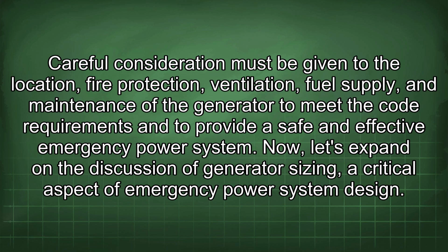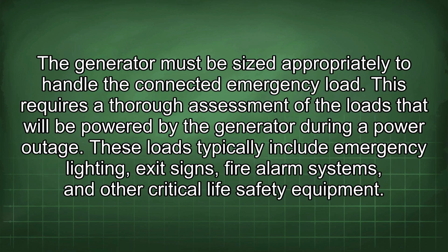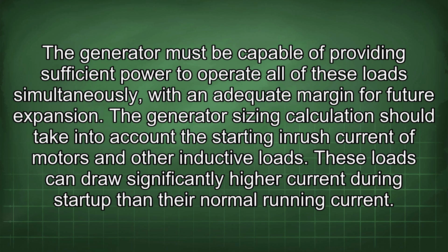Now let's expand on the discussion of generator sizing, a critical aspect of emergency power system design. The generator must be sized appropriately to handle the connected emergency load. This requires a thorough assessment of the loads that will be powered by the generator during a power outage. These loads typically include emergency lighting, exit signs, fire alarm systems, and other critical life safety equipment.